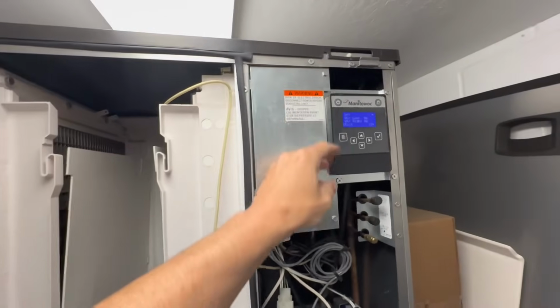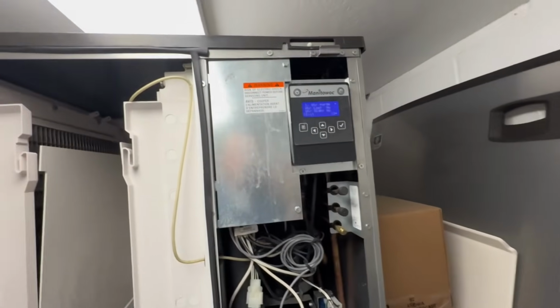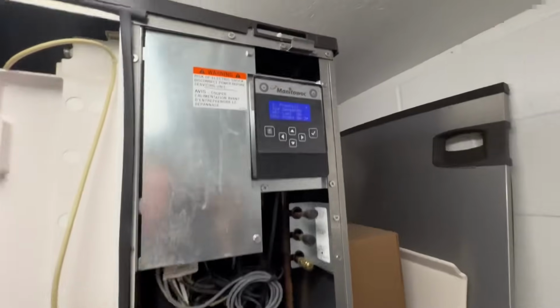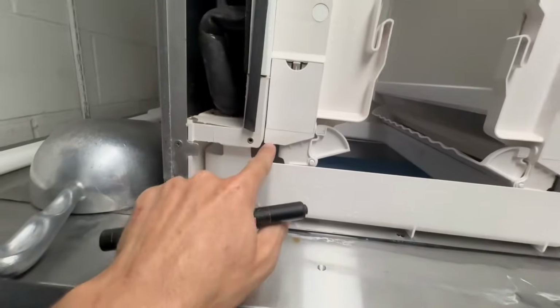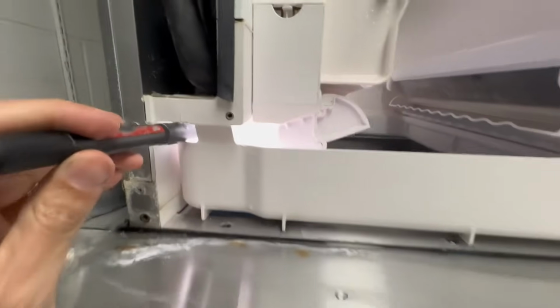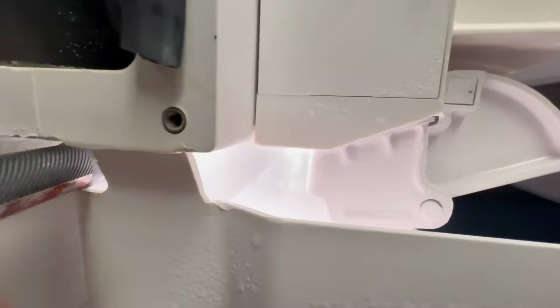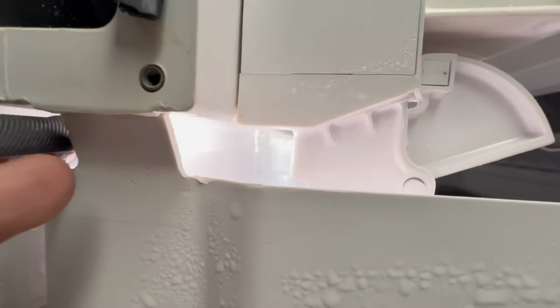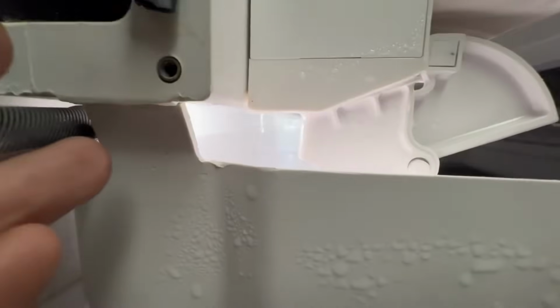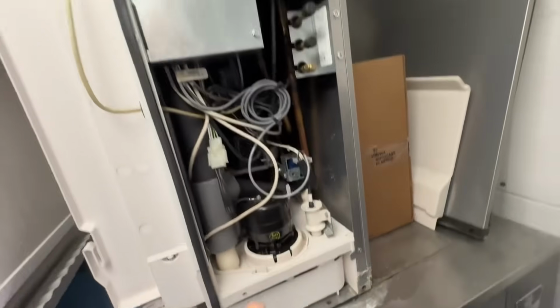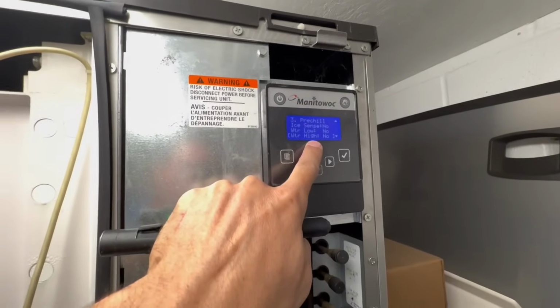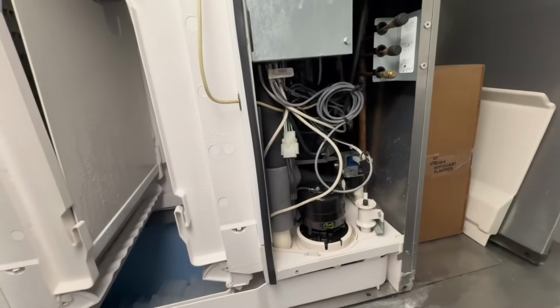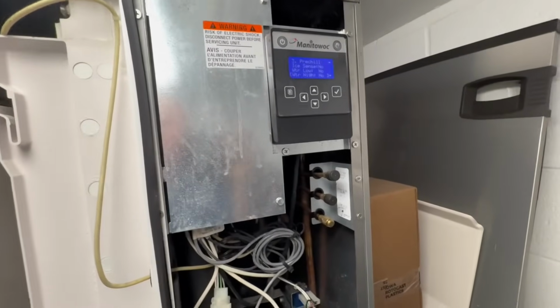I'm going to turn the machine on, time a cycle, see what happens, and go from there. We are in pre-chill now. This is when the water tank, or water trough, fills up with water, and the water is flowing into the evaporator, but it is pretty slow. I'm wondering if it'll fill up in time and what will happen with these two while it's filling and going through pre-chill. I'm going to try to find some water filters or the water valve, which is probably buried back there somewhere.